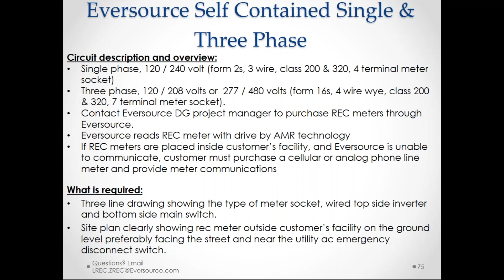Doesn't mean that you have to provide a full 3-line diagram, because for interconnection, you're only required to show a 1-line, but you can provide 3-line detail on the 1-line or in the form of just an extra detail on that same page that indicates to us that you're showing the proper type of meter, again, being a Form 16S or 9S, whatever the case may be, with the correct type of 3-line information, showing things such as, in the case of instrument-rated, polarity markings and CT or VT sizes, and in the case of all meters, showing that you're properly wiring it so that it's line or top side coming from the inverters and load or bottom side going towards the grid.